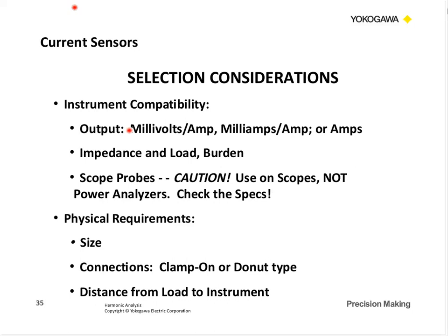Other selection considerations, of course, is the output. We've got to match it to a measuring instrument. So some of these have a millivolt per amp or a milliamp per amp output, just like our instrument transformers typically have a 0 to 5 amp output. The impedance, the load, or the burden that's put on the CT from the instrument is also very important. This is what I was talking about, scope probes. Use on scopes, but be careful hooking up a scope probe to a power analyzer, because a lot of those scope probes are meant to match the input circuit of a scope, a different type of input impedance, and we have a high input impedance typically on the power analyzer. So just be careful in how those are used.